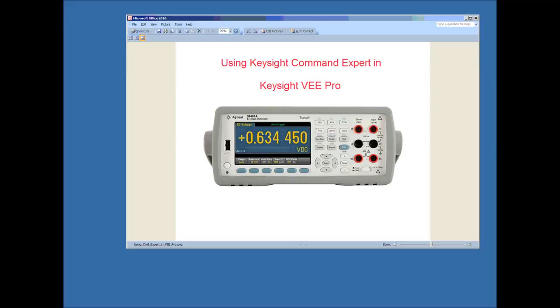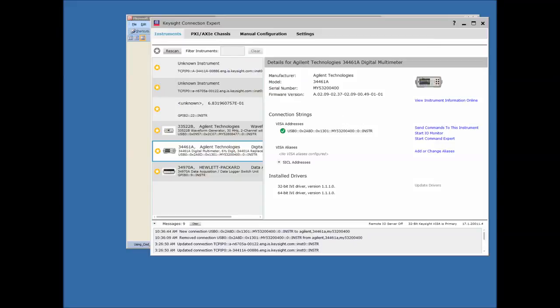The first thing you want to do is make sure you have connectivity. In the IO library suite from Keysight, there is a tool called Connection Expert. We want to bring up Connection Expert here to show you that this instrument has already been identified. I have it connected to the computer via the USB port. Here's the unique USB VISA address string.